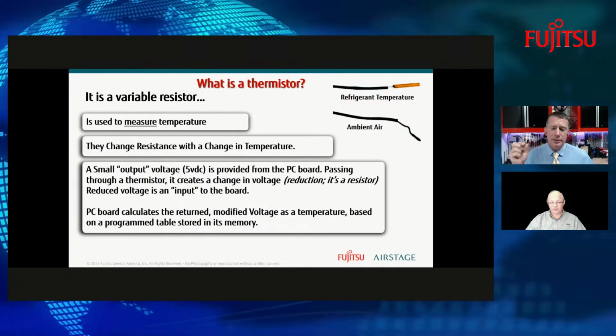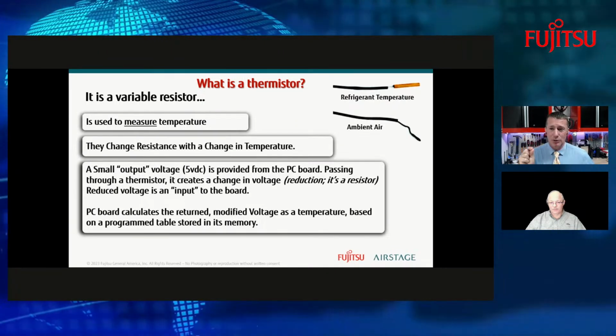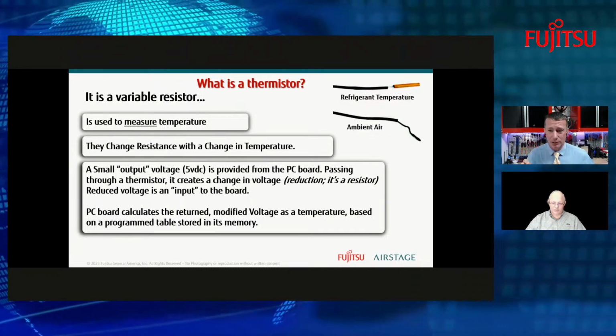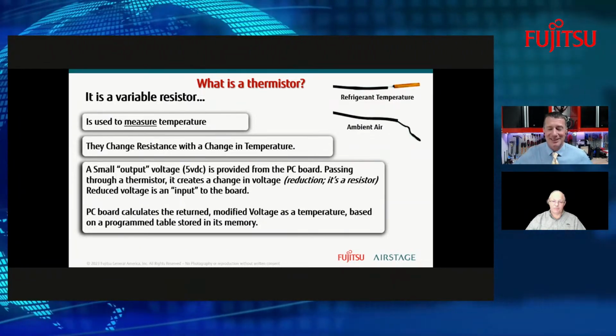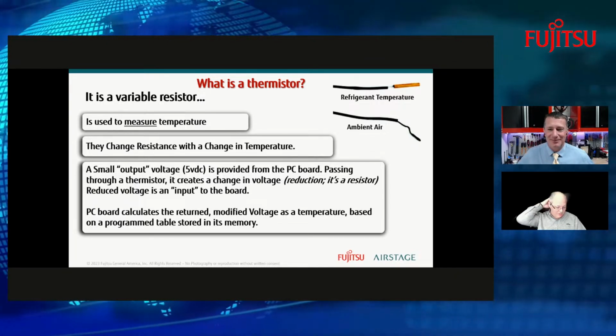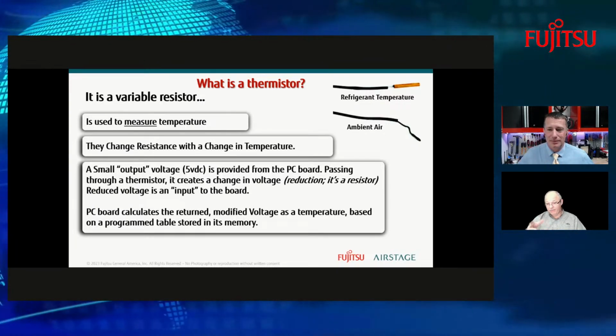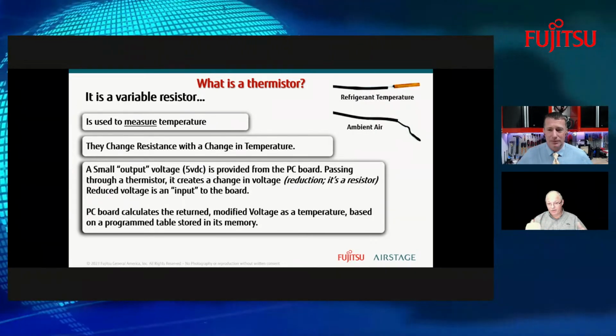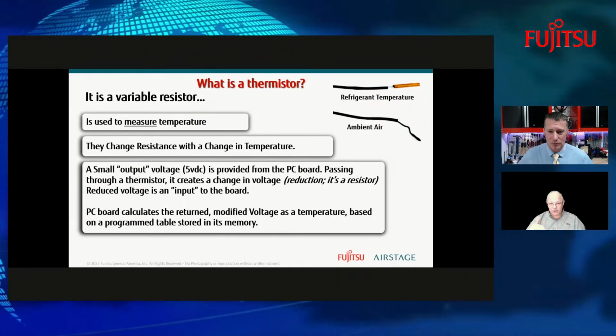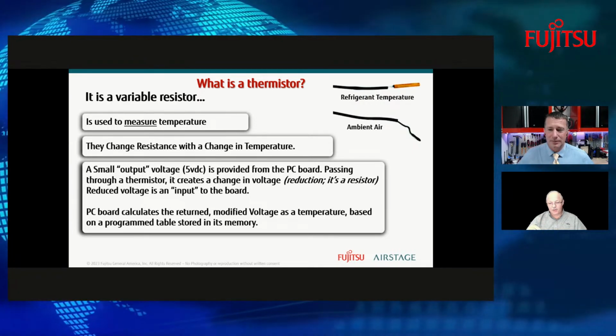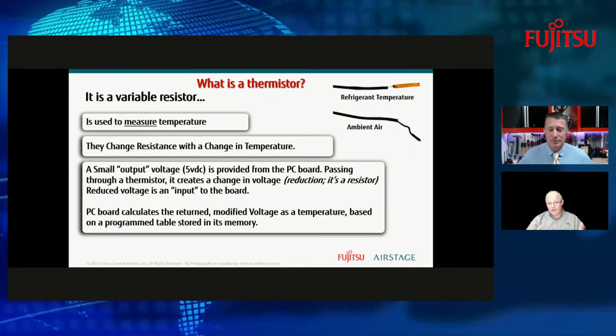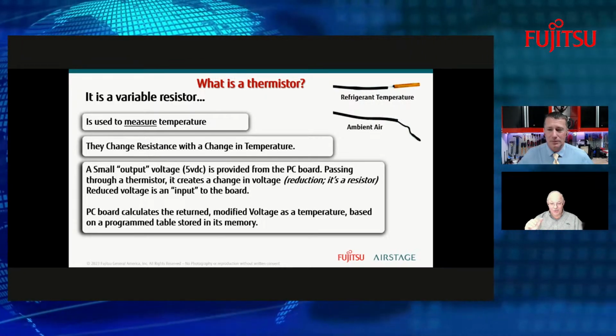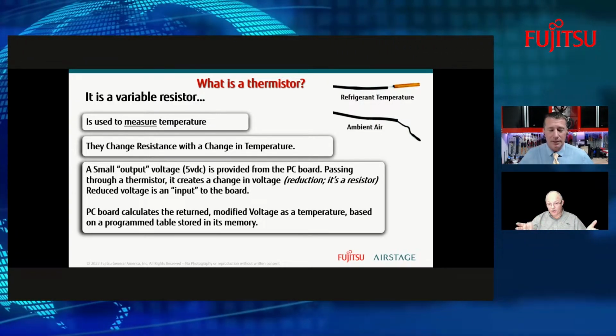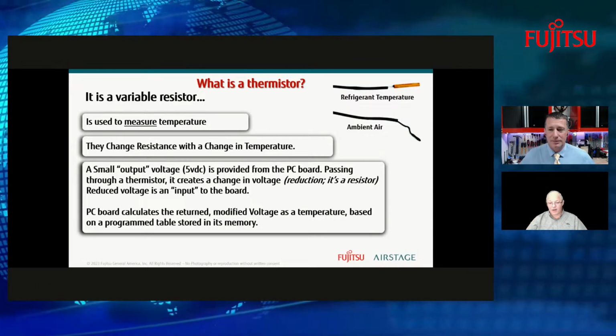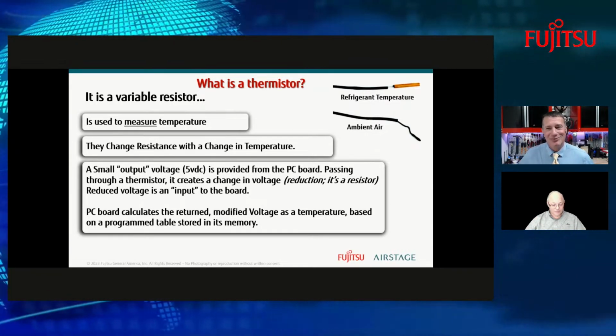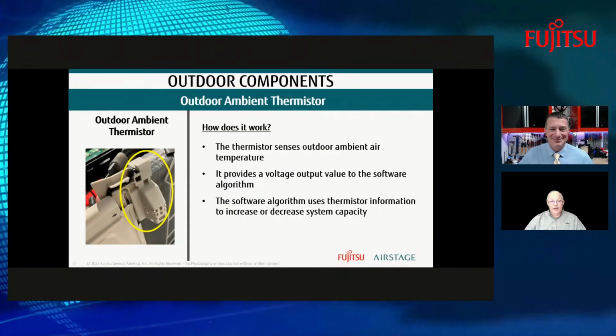Now, in your service manuals, do you provide the chart that shows what those output voltages are based on temperature? Yes. So if somebody wanted to go in and actually check a thermistor to see if it's within the ohm range it's supposed to be, you just need to know what the temperature is at that thermistor. Typically when you get that number, you're going to be 10% high or low of that number. If you get outside of that range, then you've got a bad thermistor. Okay, 10% rule of thumb. Good to know. So that is available.